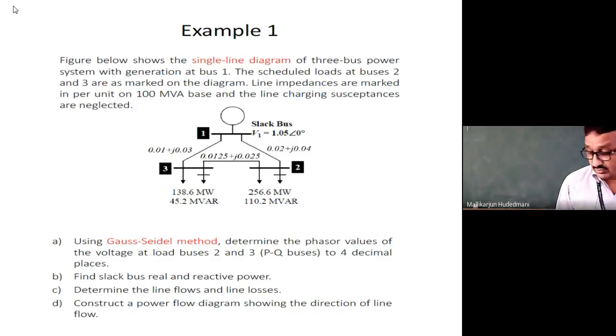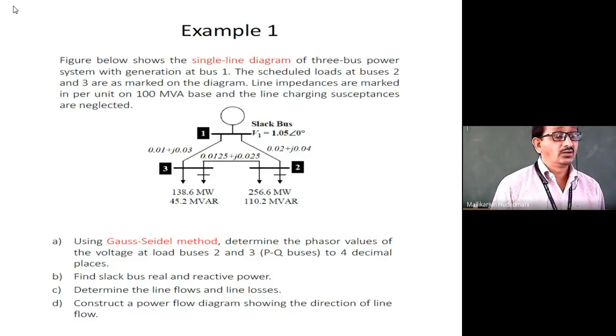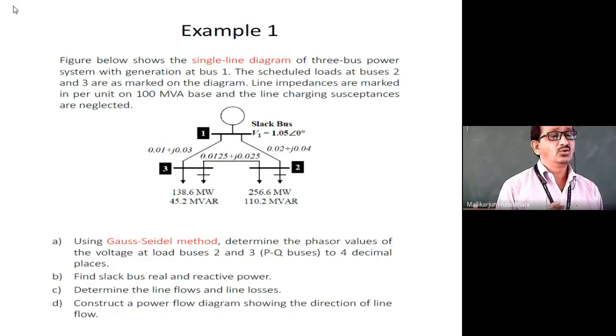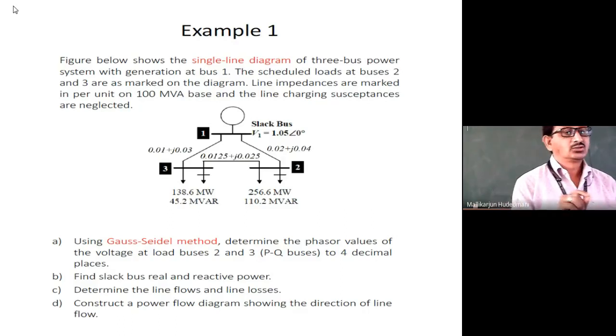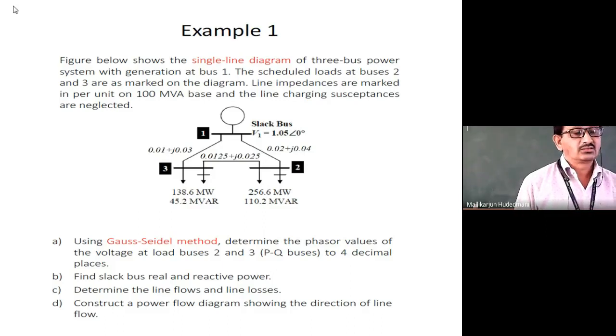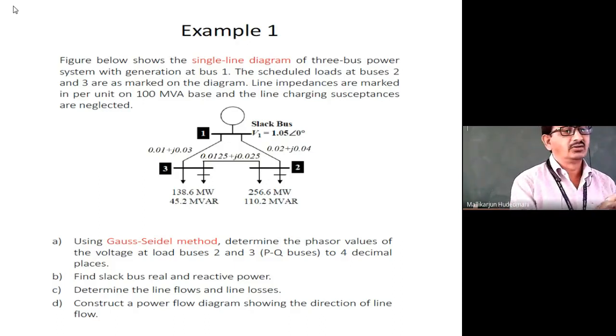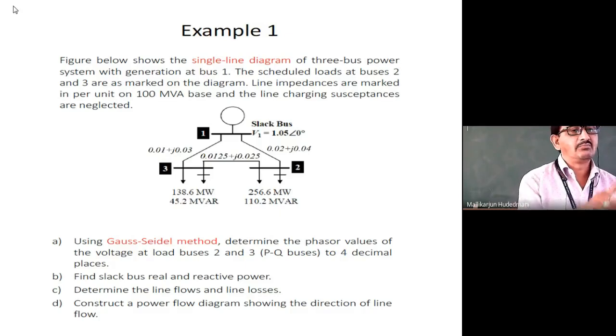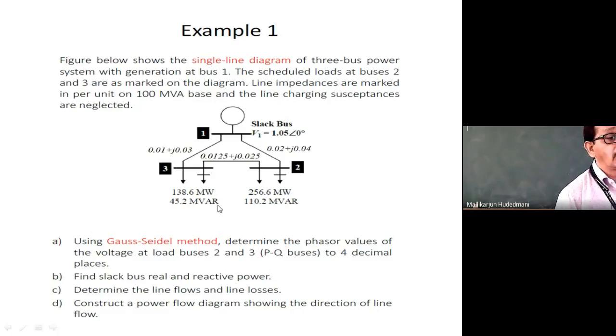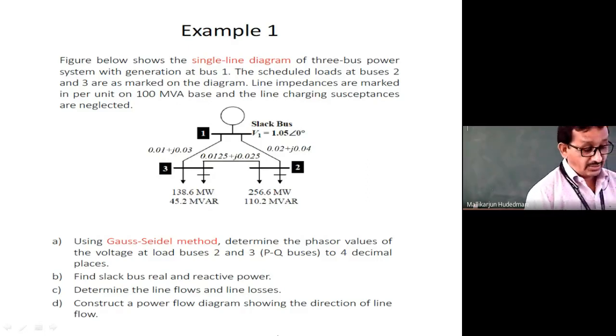We are asked to compute voltage solutions at the end of iterations one, two, three, and so on. This problem was run on a computer for seven iterations; for academic purposes we need only one iteration manually. The solution covers voltage magnitude, phase angle, transmission line losses, and power supplied by the slack bus using the Gauss-Seidel technique. The transmission line data is given as impedance, so megawatt and MVAR values must be converted to per unit using base value of 100.